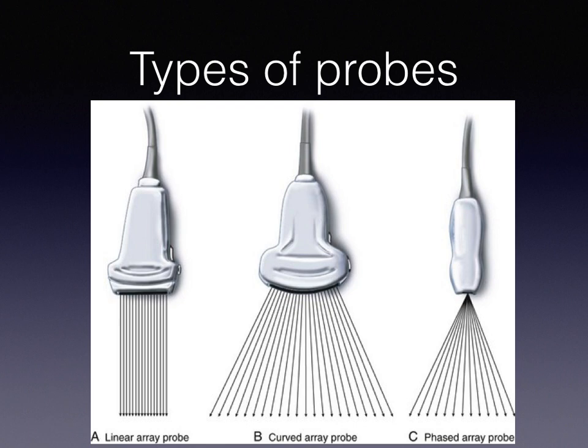The first one, linear array, is a high frequency, low penetration, high resolution probe. Helpful, as before, for evaluation of vessels, procedural medicine, evaluation of skin and lymph nodes. Then we have a curved array, low frequency, which scans a larger part of the body. It has low resolution, high penetration, and is very useful for abdominal evaluations. The phased array probe is low frequency, but as you can see, the ultrasound comes from the center of the probe, making it ideal to look in between the ribs, and therefore it is the probe we use the most to see the heart.